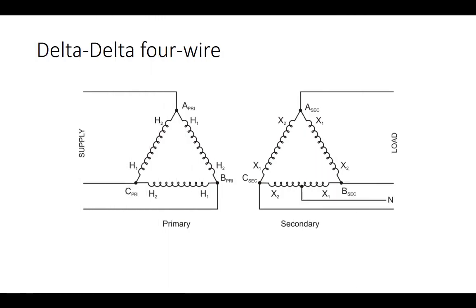Part 6 for three-phase transformer connections is actually objective 4, which is the delta to the delta 4-wire connection. It is not a common three-phase transformer connection. It is used sometimes in certain locations, not an awful lot. It is sort of a unique connection.